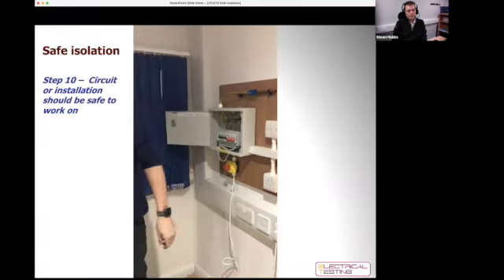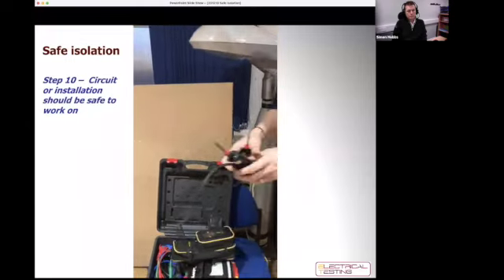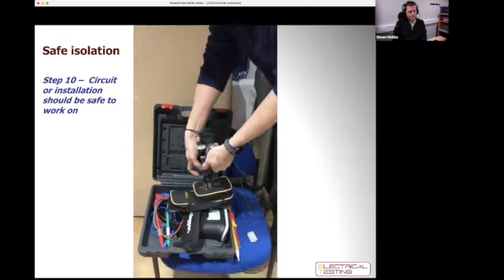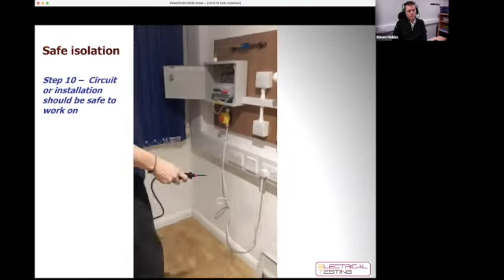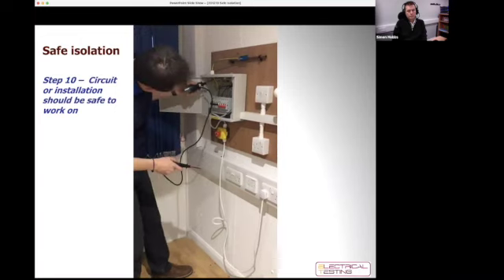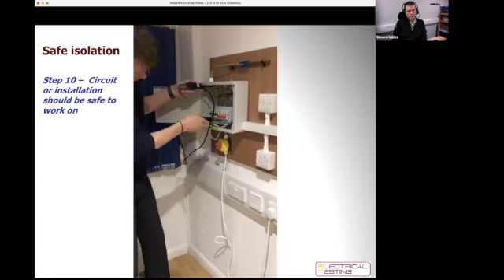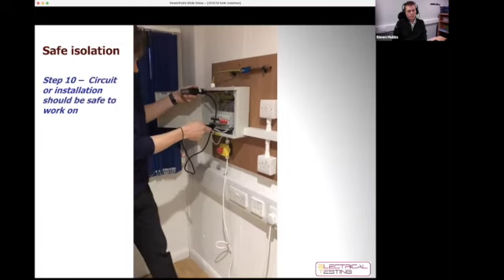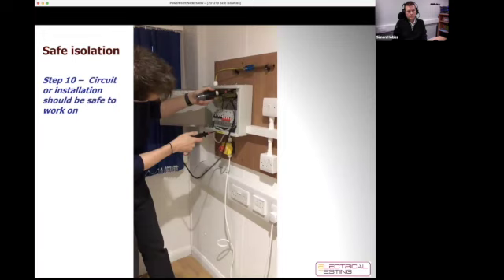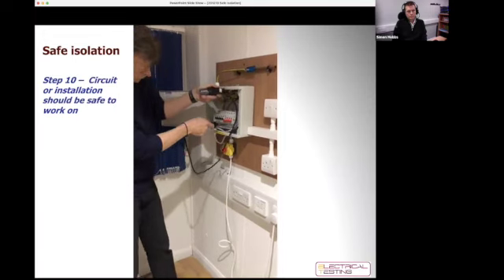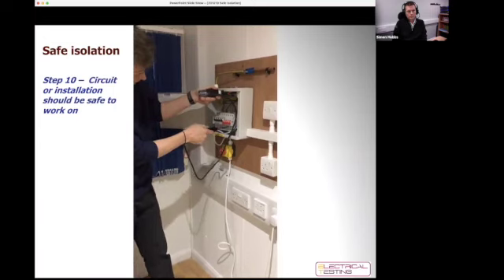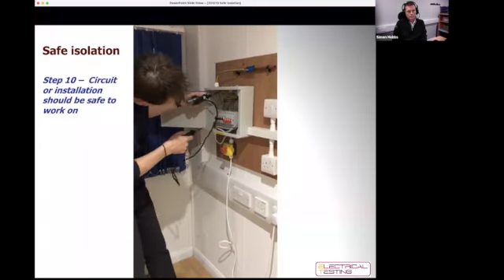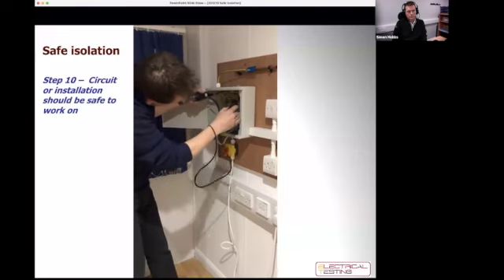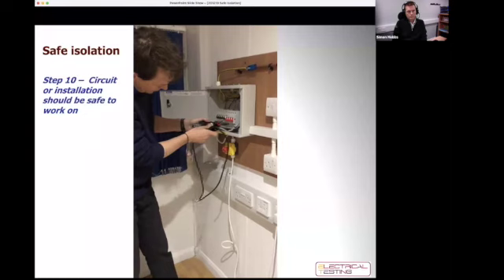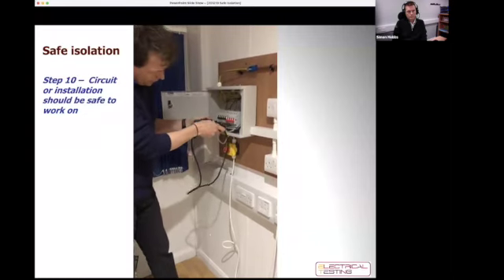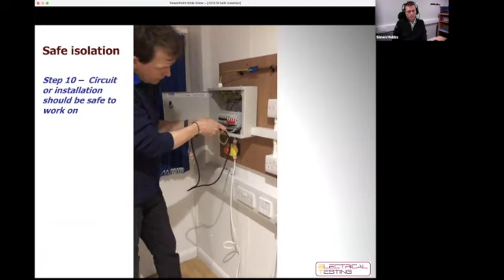Okay, so next thing I'll use an approved voltage indicator or test lamp and I'll prove that it's working on a known live source or proving unit. That's good. And I am then going to carry out the test. I'll talk you through what I'm doing. So I'm going to go earth to line 1, earth to line 2, earth to line 3. I'm going to go neutral to line 1, neutral to line 2, neutral to line 3. I'm going to go earth to neutral, and then I'm going to go line 1 to line 2, line 1 to line 3, line 2 to line 3.